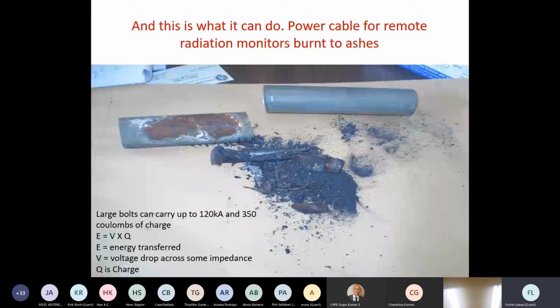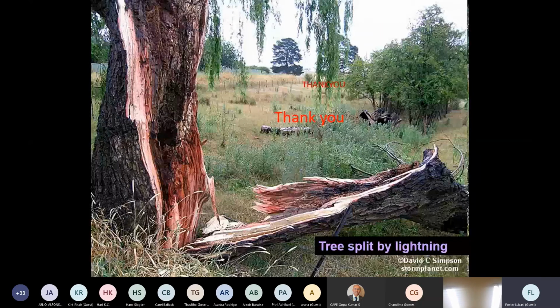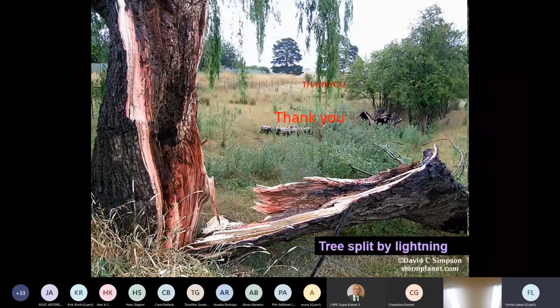And this is what it can do. Here we had a power cable for our radiation monitors. I hope the Radiation Protection Authority is logged in, because this is the equipment where the power supply cable was struck by lightning. We are also told that a large bolt can carry up to 120 kiloamps and 350 coulombs of charge. So you can calculate the energy from those using the equation. And as you can see from the energy and power of lightning, a huge tree like this was struck and split into pieces.